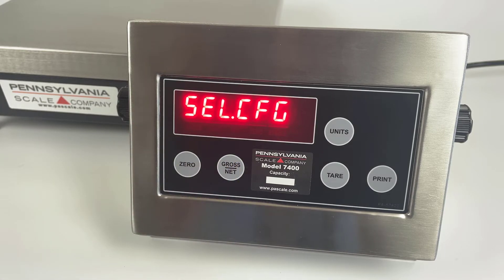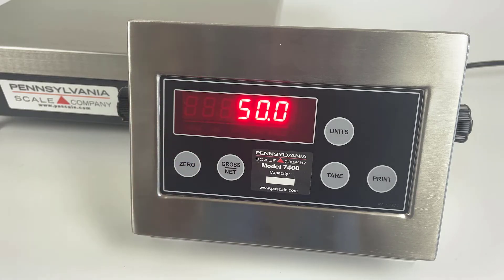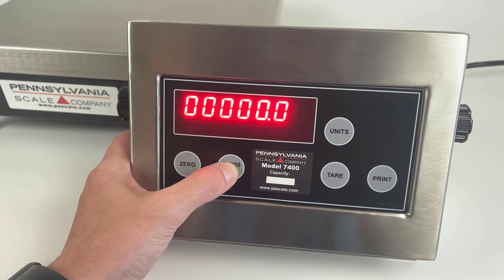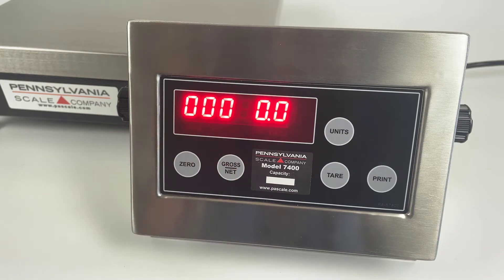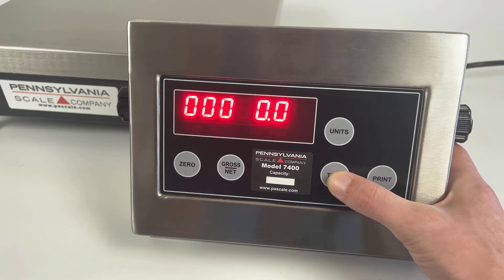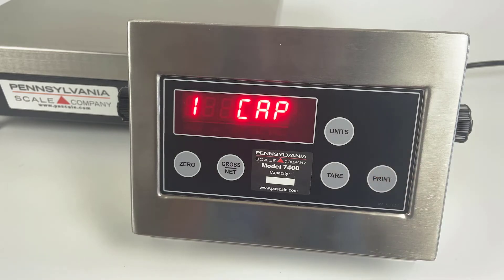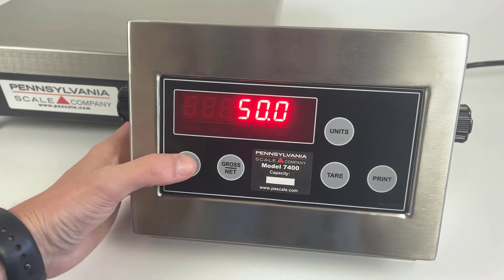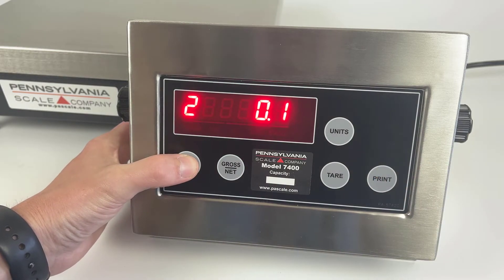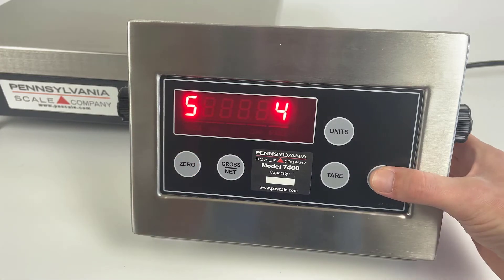First, we'll enter the SEL.CFG menu to check the capacity and resolution. Press the zero key to enter the menu. For capacity, use the gross/net key to select the tens place and the tare key to increase the value. Press the print key to confirm. The zero key scrolls through the various options, and to back out to the main menu, press the print key.